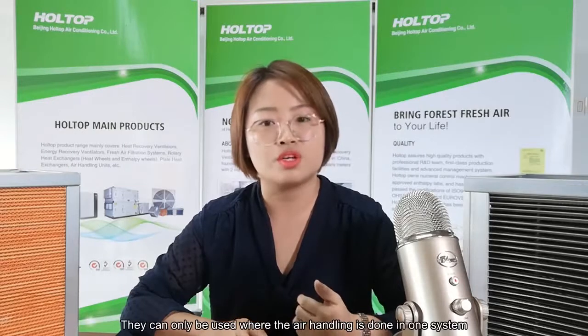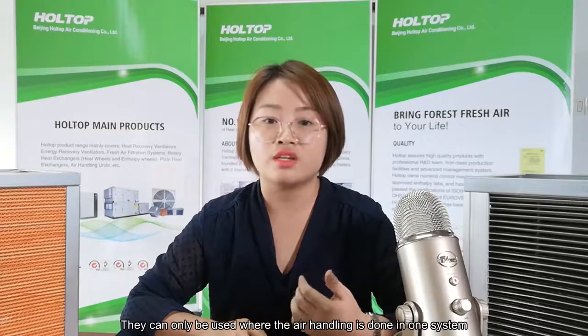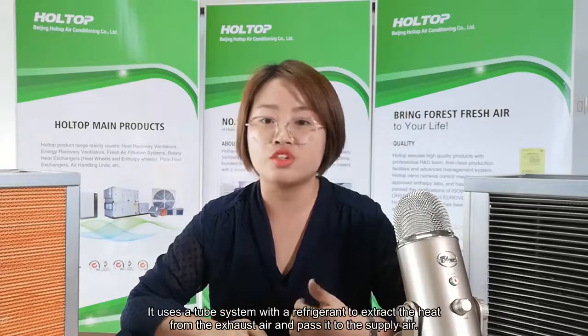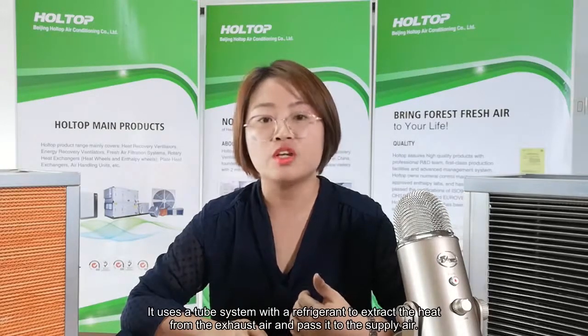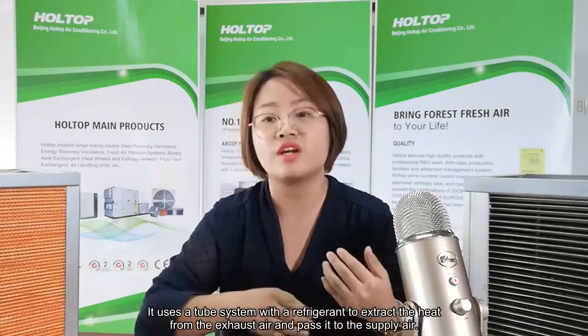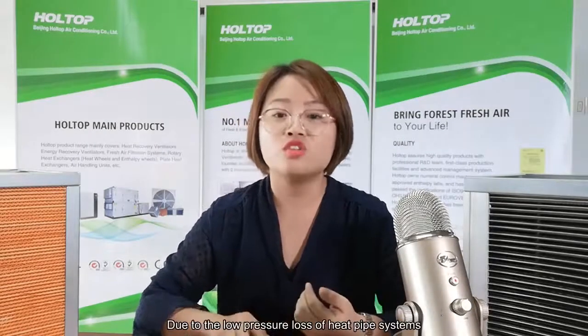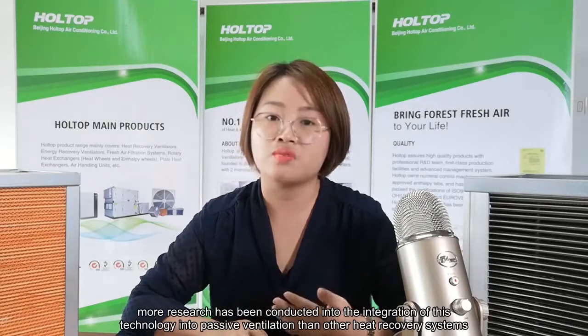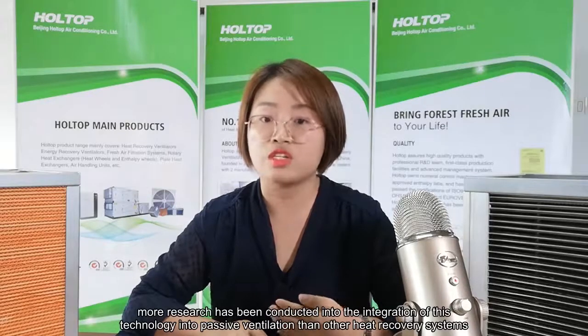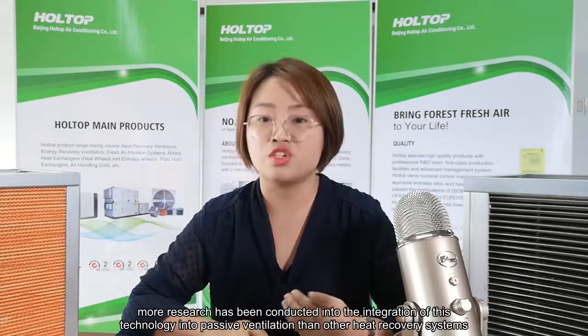And the third type is the heat pipe heat exchanger. Compared with the other heat exchangers, heat pipes are the lowest maintenance. They can only be used where the air handling is done in one system. It uses a tube system with refrigerant to extract the heat from the exhaust air and pass it to the supply air. Due to the low pressure loss of heat pipe systems, more research has been conducted into the integration of this technology into passive ventilation than other heat recovery systems.